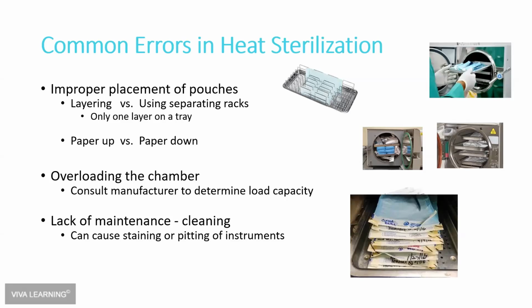And your sterilizer also will come with load capacity determinations, so that it will tell you how many pouches or how many cassettes or how many combo of pouches and cassettes you can put in one particular load. So make sure that you look at all of those parameters, because your spore test may be working. You may be passing your spore test, but that may not be indicative of how you normally load your sterilizer. So it may be giving you a false sense of security. And make sure that you keep your sterilizer clean. It should be cleaned. In most cases, manufacturers say use a sterilization chamber cleaner on a weekly basis. Keep it functioning well, and it can help avoid pitting or staining of instruments.